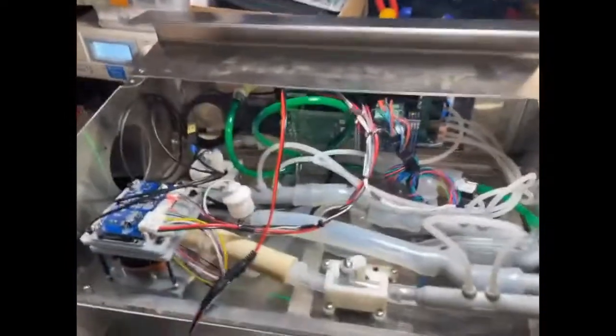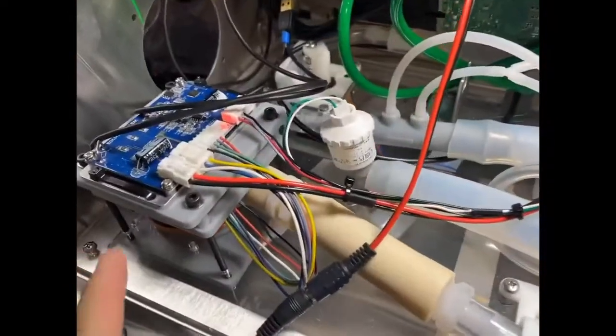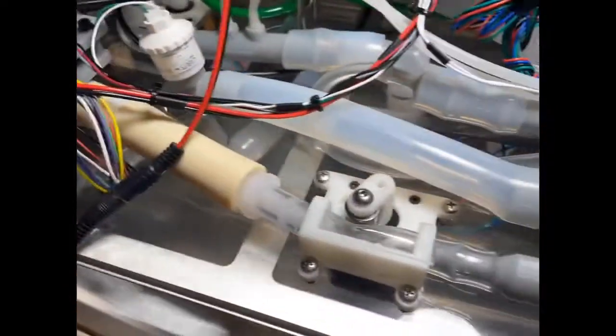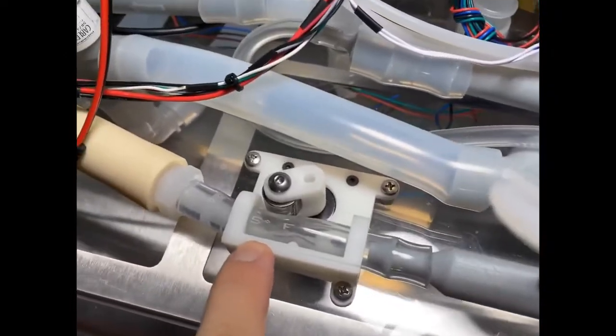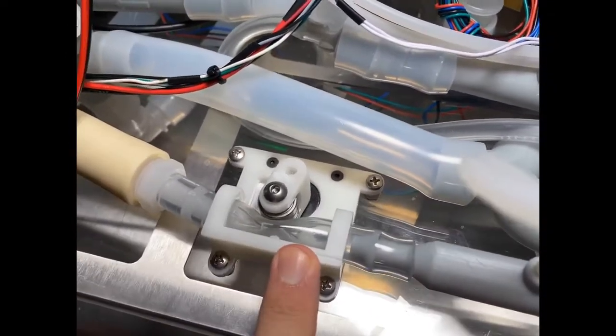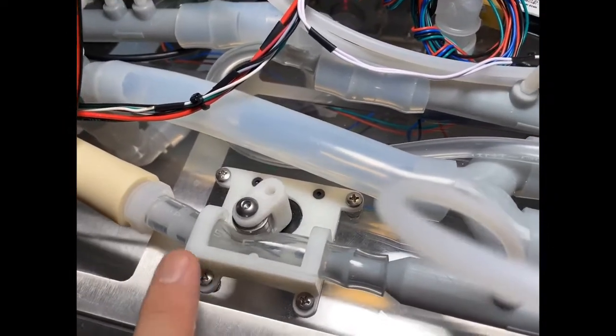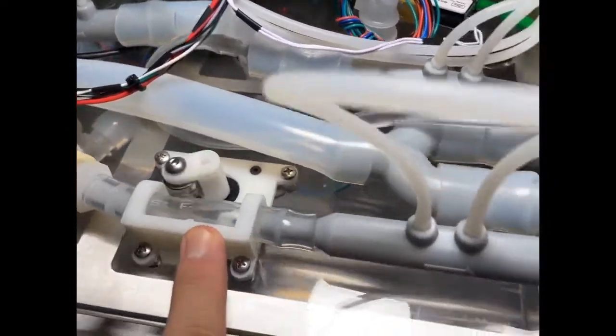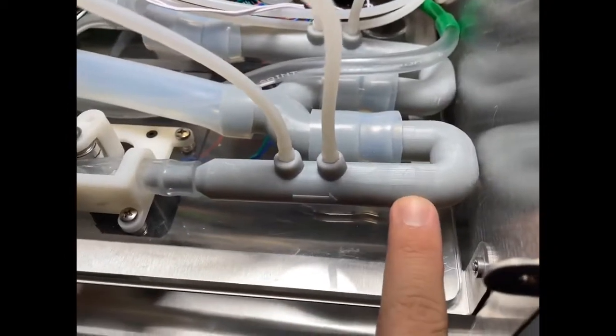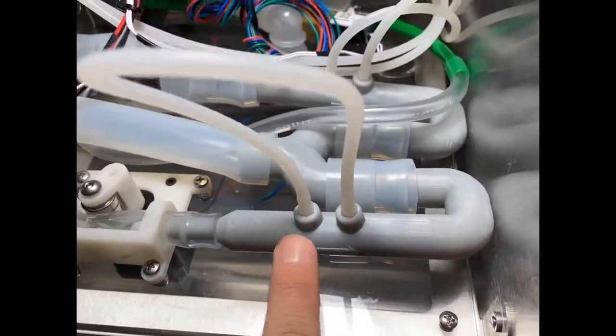All right, so in here we have the blower, which is doing ambient air intake, which then goes to our custom designed stepper motor based pinch valve, which gives us a fast response rate and a low pressure drop across the valve. We have our custom designed and 3D printed Venturi sensors, which is how we do flow.